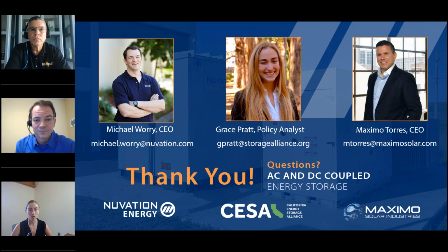Awesome. For Maximo, in your Puerto Rican microgrid, is the genset ever providing power at the same time as the battery? Yes, the genset might be providing power to the building, but we will still be providing power from solar energy to the load. So if the generator fails, our battery system will pretty much isolate this load totally from the building when the power goes out. It's totally protected by batteries and the solar energy system. Okay.